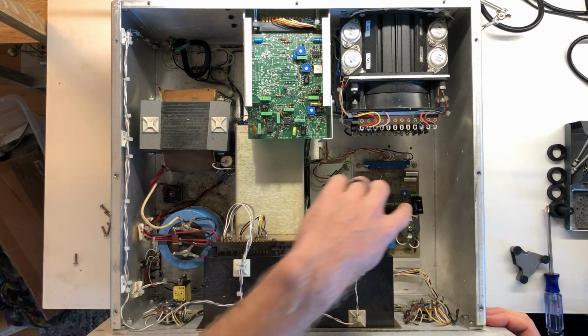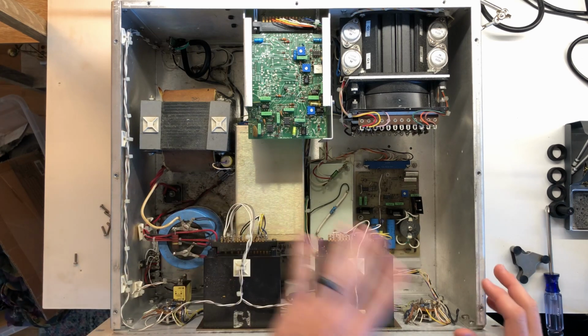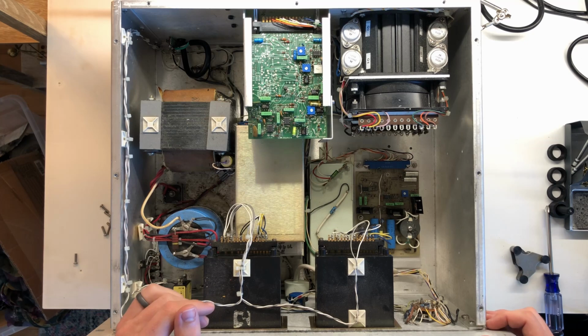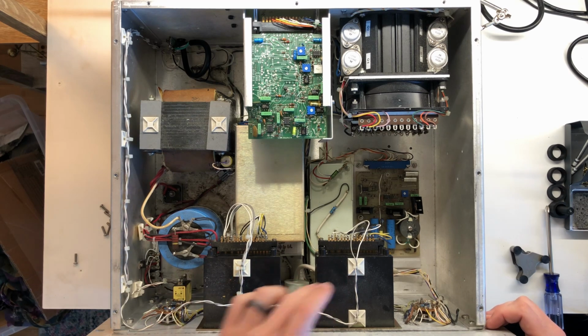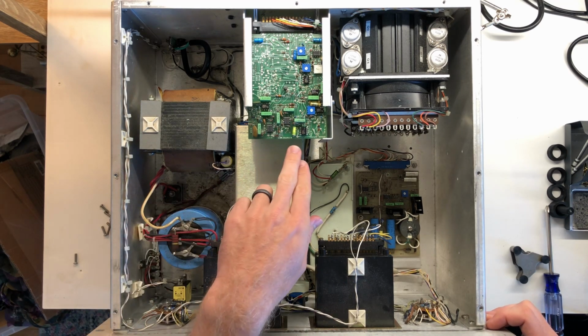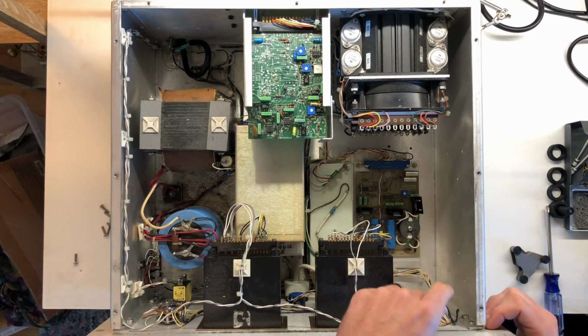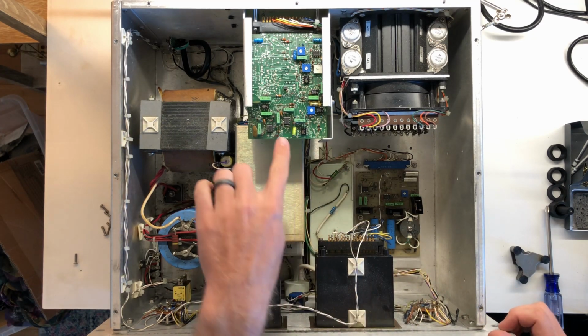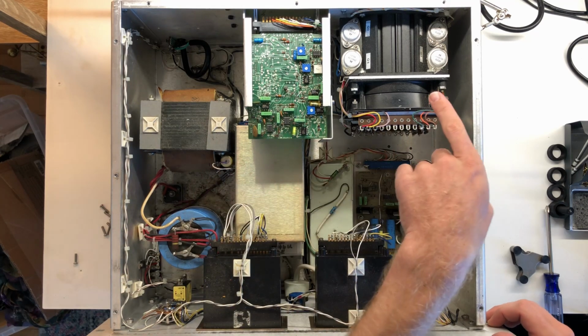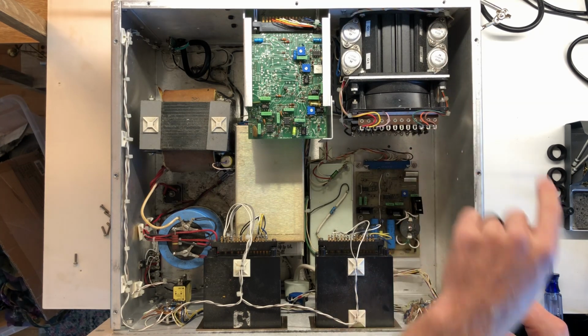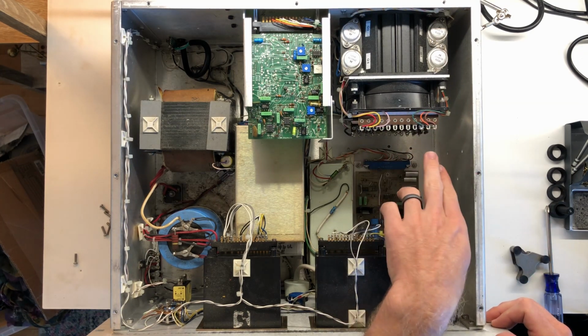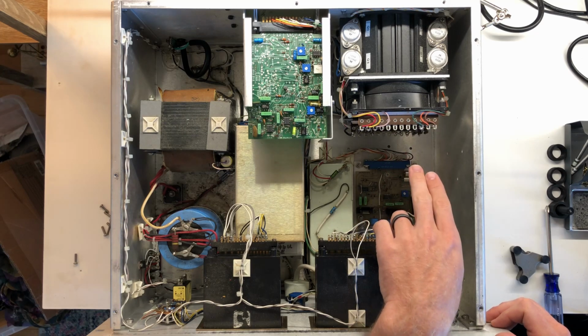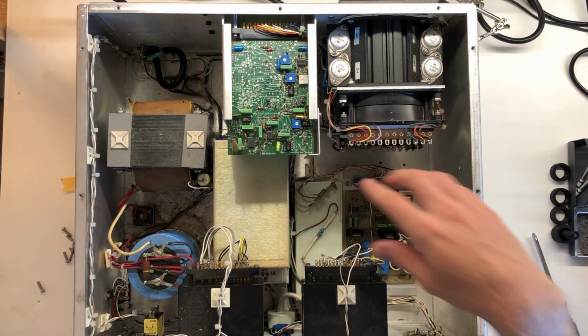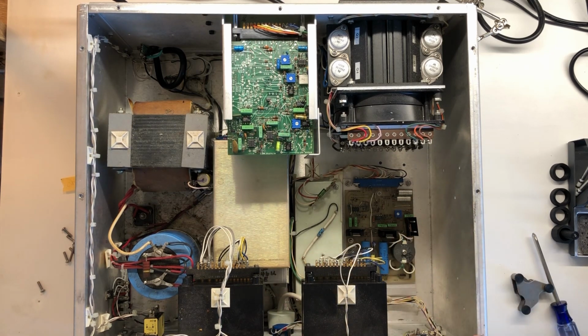So we have 3 modules here that correspond to the 30 kV, 8 kV, and 1 kV outputs. All those outputs are completely independent with their own modules. It looks like we've got our 3.5 digit 7-segment displays here, and then some sort of control board, with wires all routed to the switches and dials on the front. So this is the brains of the operation, and here we have some power transistors and a set of resistors cooled by this fan. It's relatively simple circuitry for controlling all 3 supplies.